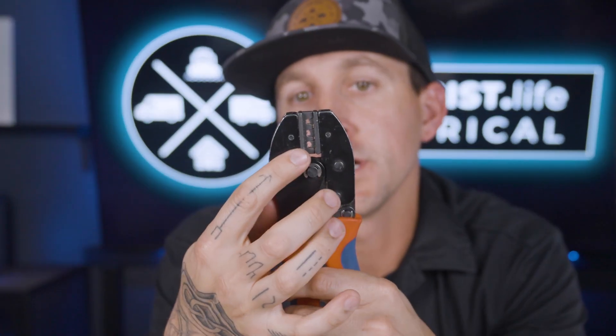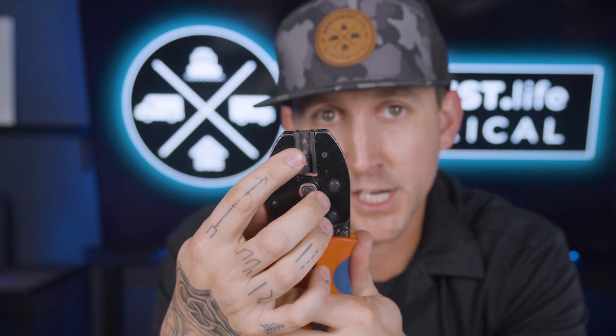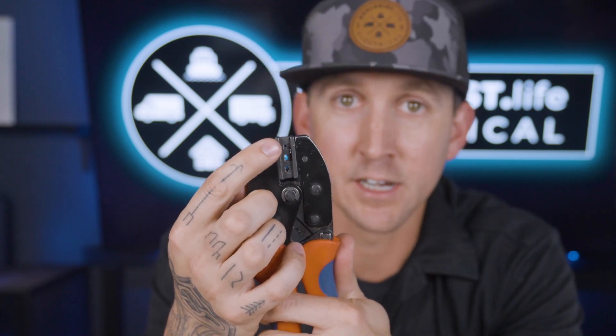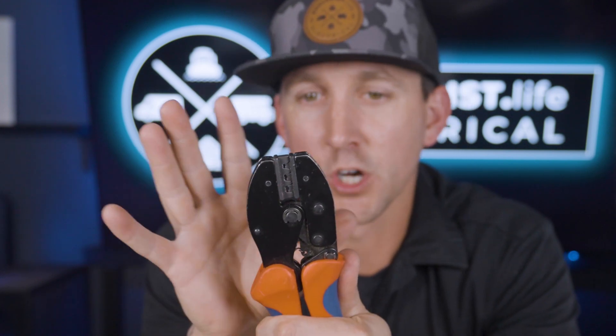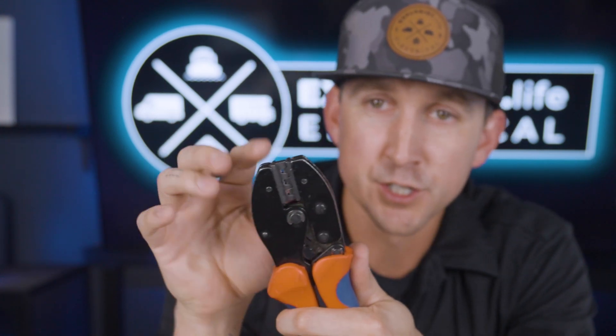It's also worth noting that these crimpers in particular have three different spaces. The largest one is for 10 to 12 gauge wire, the middle one is for 12 to 14 gauge wire, and the smallest is for 16 to 18 gauge wire. We only install 10 gauge PV wire and PV connectors in Explorist.life system designs, so we're only going to be using the biggest space of the crimpers for our purposes here.